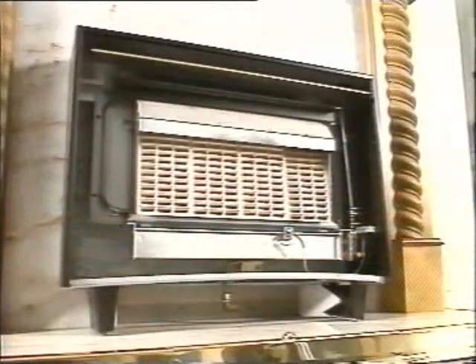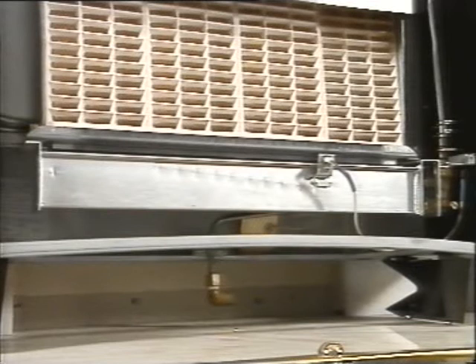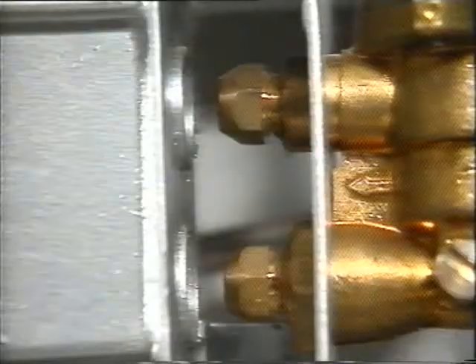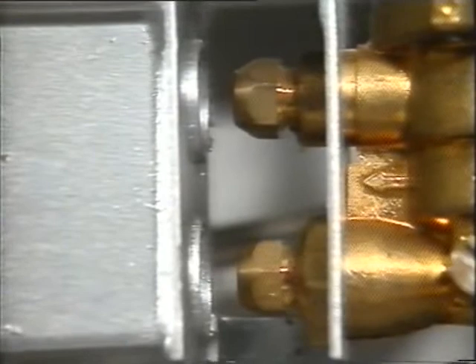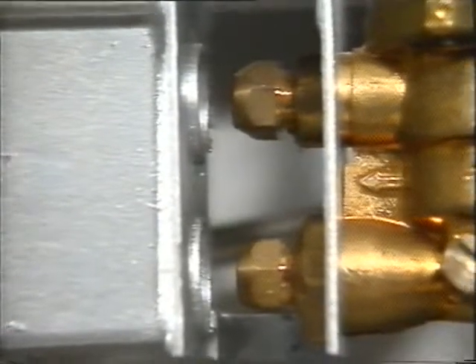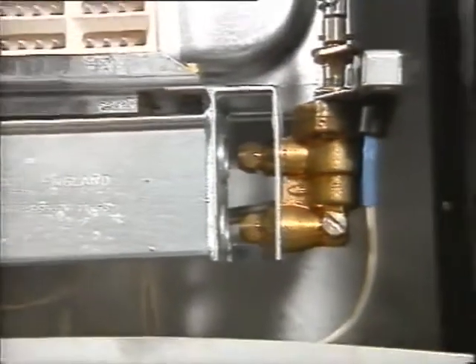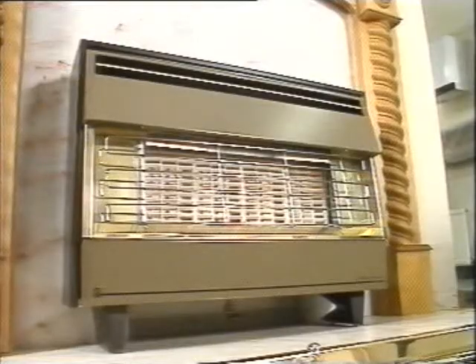stops the box overheating. The burner can either be simplex, in which all flames come from a single injector, or duplex, which allows various permutations. There are different injectors, and the burner itself is divided into sections to give a greater choice of settings for heat output. The fire guard is fixed to stop combustible material coming in contact with the radiants.